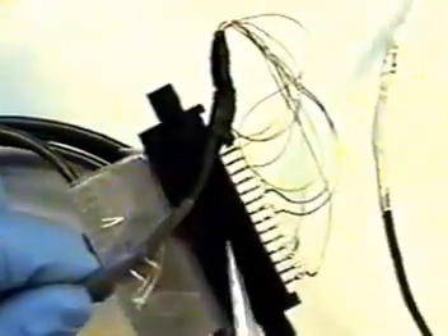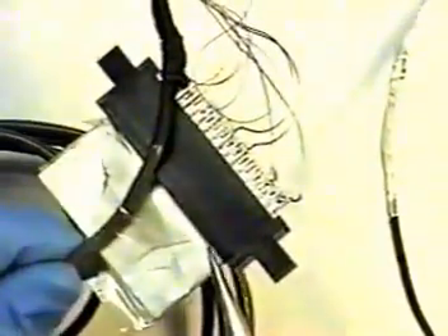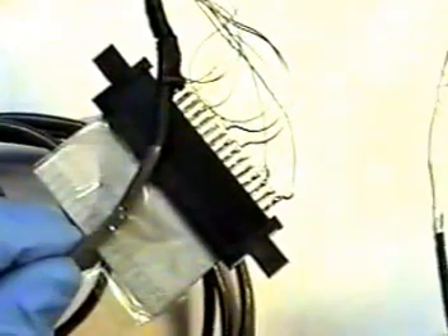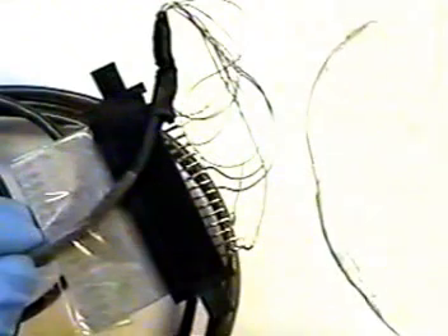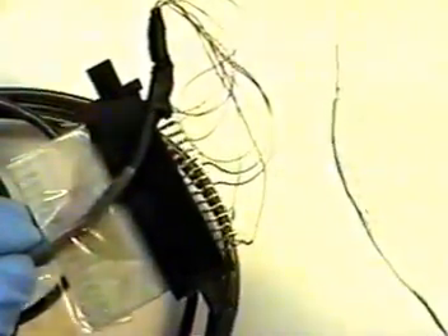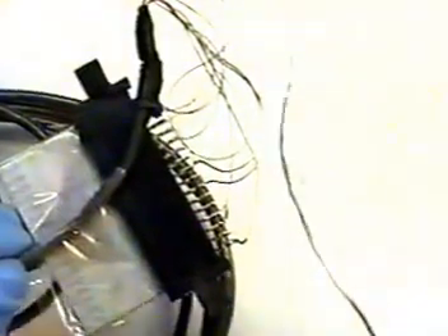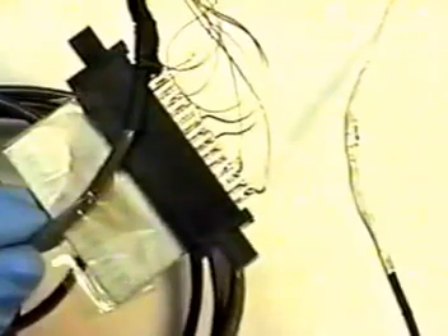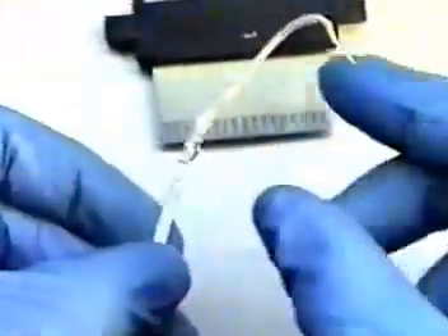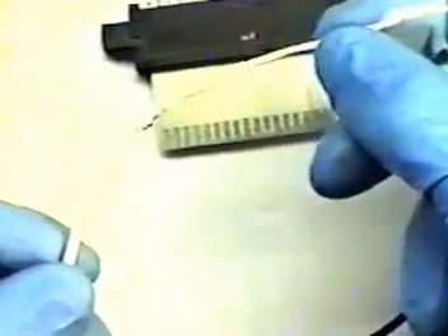Please note, if your CHA CCD wiring assembly was attached to a static ground block, it will be required to wrap in white Teflon tape. Carefully cut or unsolder each CCD wire from static control block and wrap in the white Teflon tape previous to pulling through body control section. Always be sure when wrapping CHA wires with white Teflon tape that you are statically grounded as not to damage the CHA CCD chip.